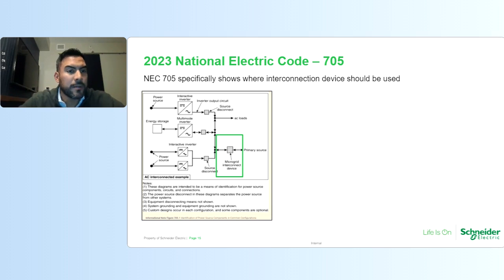If you go up one, you see a multimode inverter. This is the energy storage system. Energy storage systems have a bidirectional inverter, so they can either charge, acting as a load, or discharge out into your AC system, acting as a power source. So that's really where the advantage comes for an energy storage system. And if you notice there, each of these inverter-based resources has a source disconnect. The source disconnect is still required by code, right? So if you want to disconnect your PV system, you still require one for code, whether it's for maintenance or service, to ensure that system's offline.